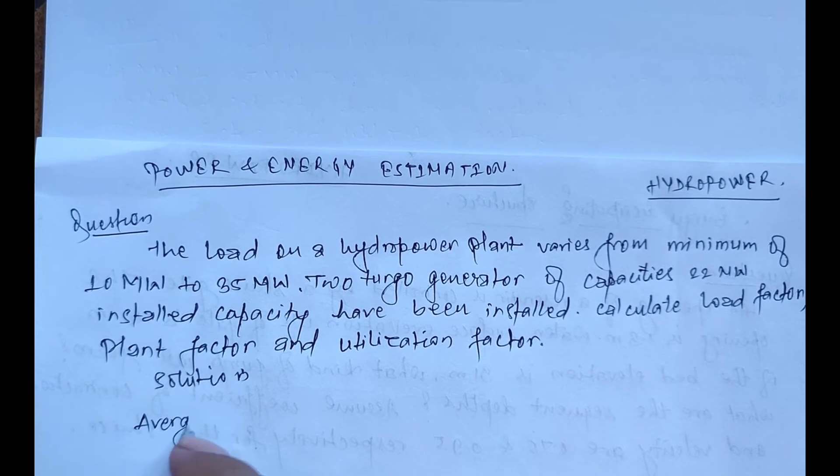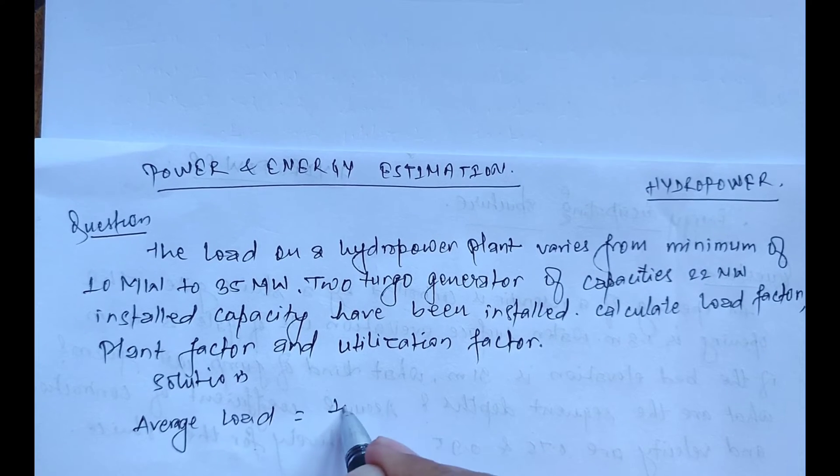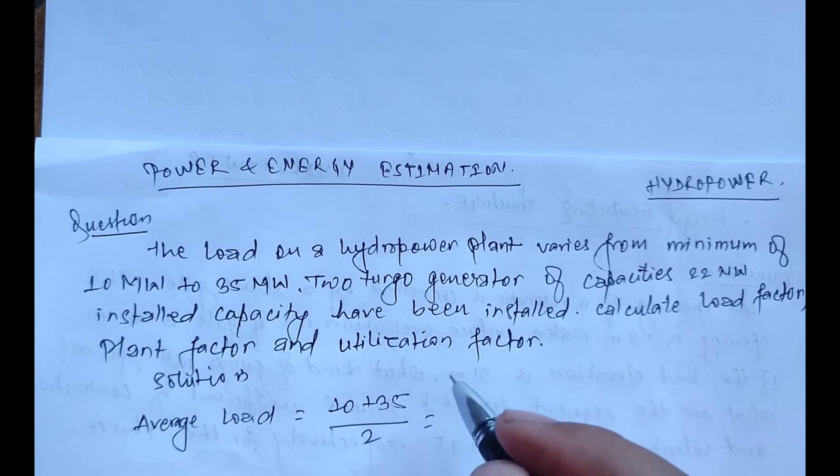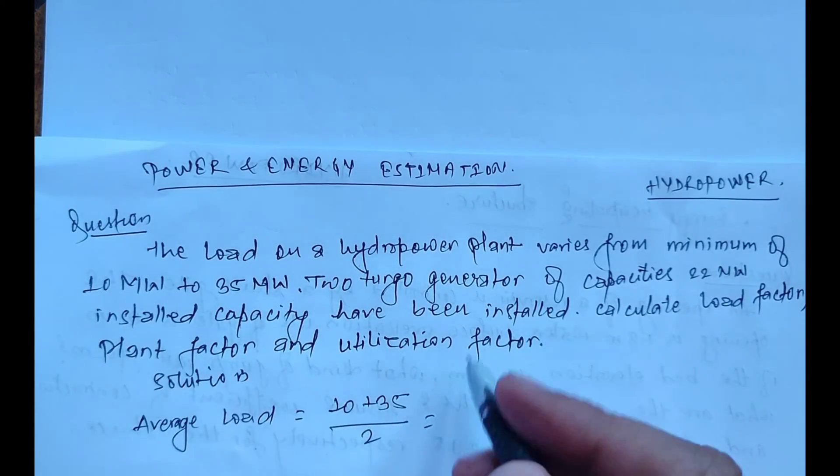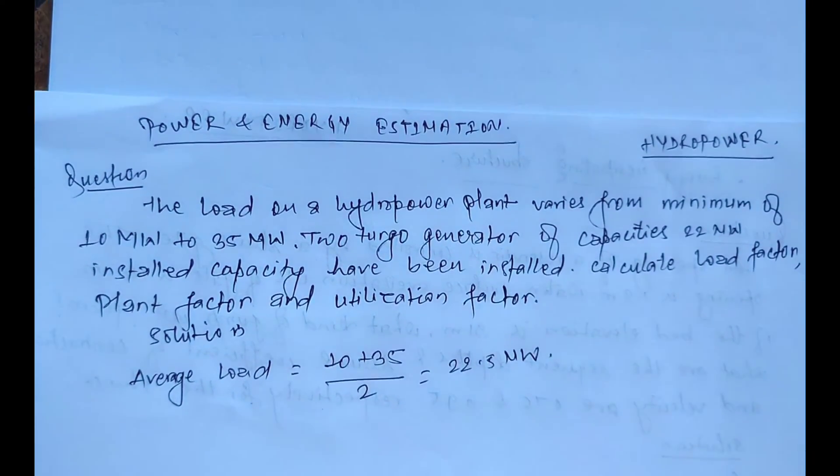Average load equals 10 plus 35 divided by 2, because first of all we will calculate the mean load. That is 10 plus 35 divided by 2, which means 22.5 megawatts.